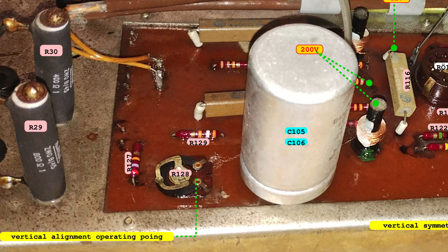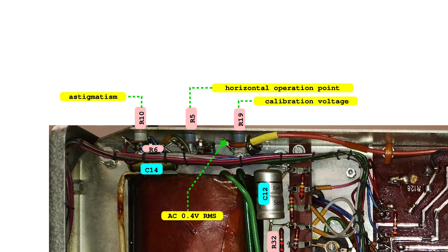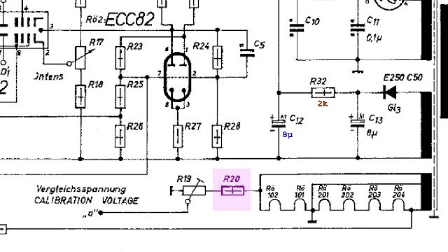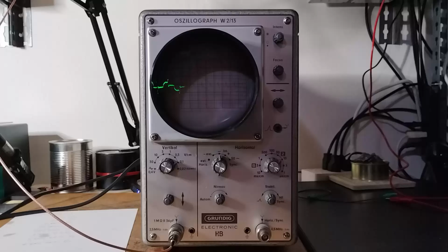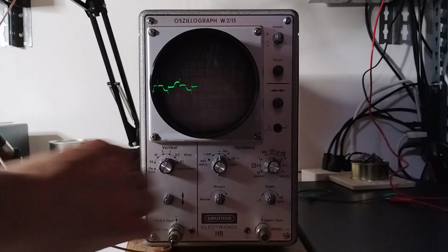Calibration voltage. According to the schematics, from the trimmer resistor R19 it is possible to set and get a sine wave of 0.4 volt RMS, which could be used to calibrate the vertical scale on the oscilloscope. During the restoration it was attempted to set the proper value of 0.4 volt RMS, but without success. It is possible that R20 and/or R32 are out of value. But even if the correct voltage could be set, the signal comes out so distorted. This is due to today's appliances making all that noise in the power lines that it would be useless to rely on such a point of reference.